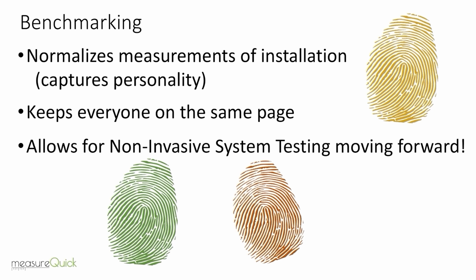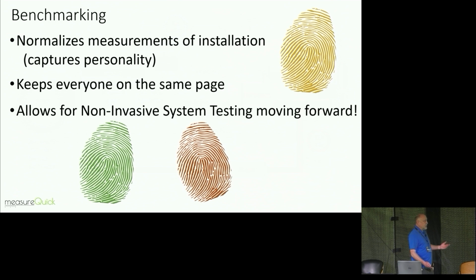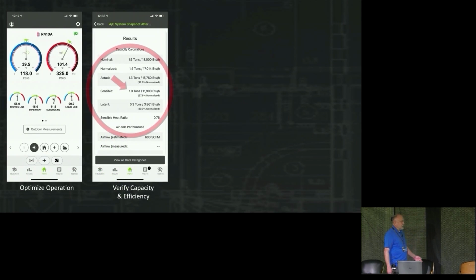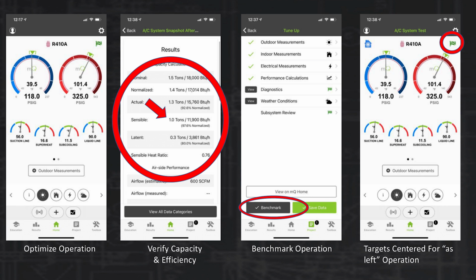So if we benchmark the system with MeasureQuick, we can literally test it with just temperature probes, everything, and it'll tell you if you're in the right ranges going forward on there. So that's the beauty of non-invasive testing. So basically, once you optimize the operation, we're going to benchmark the system, and then it's going to line up the centers on there so we can do non-invasive testing going forward.